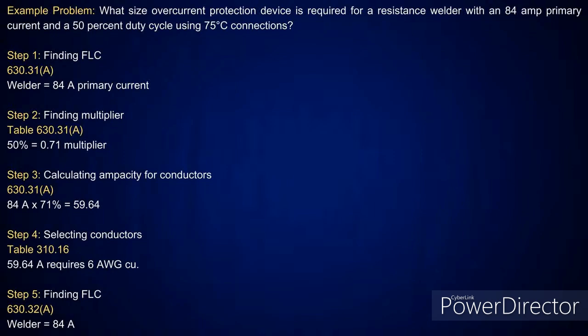It's going to come across. It's the first one in the table. It's going to give you a multiplier of 0.71. So I'll take the 84 amps at 0.71, which gives me 59.64 amps. I look at Table 310.16, the 75 degree C column. The next size above that is 65 amps, which is a number 6 conductor. All right? Then I'm going to do my overcurrent device.